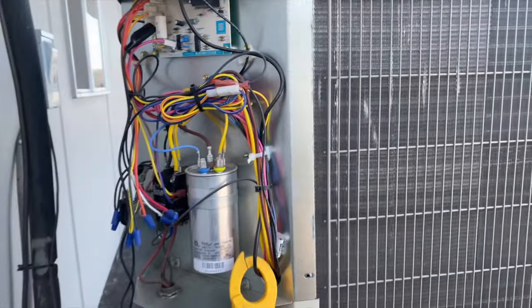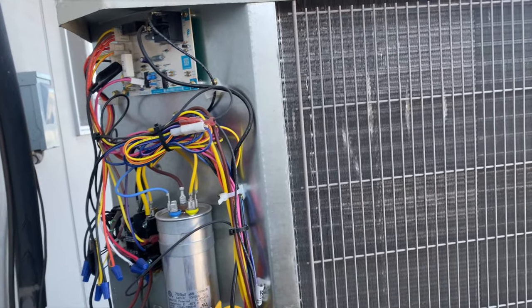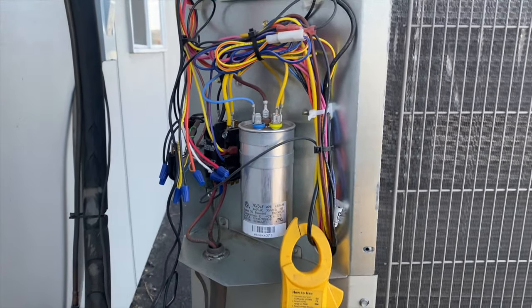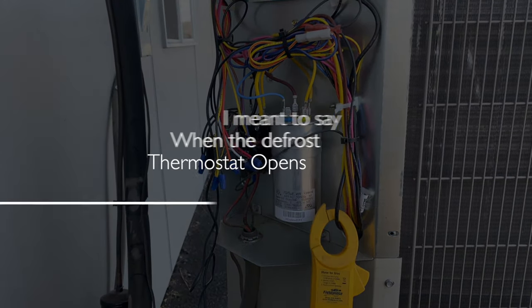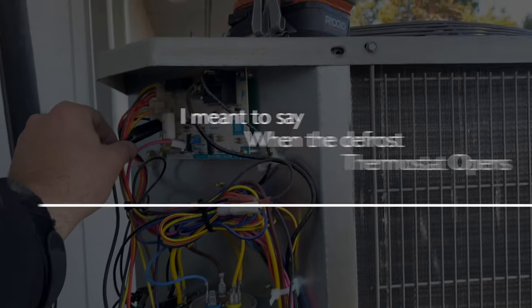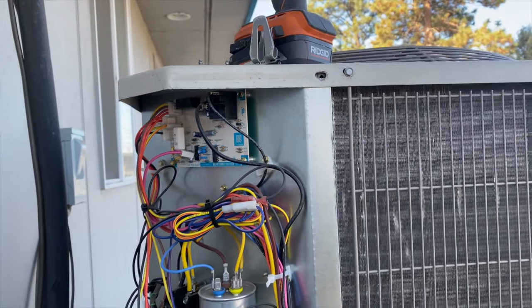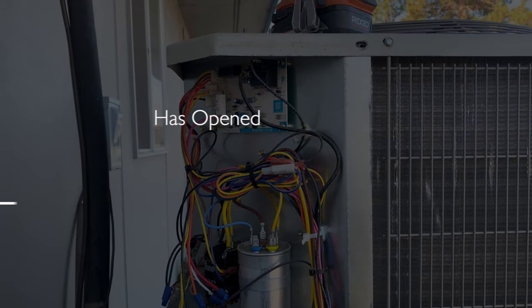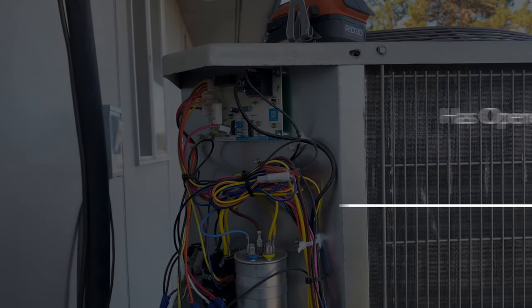I'm not sure exactly for Carrier how long it'll run in defrost, but generally it's going to be 10 minutes or until the defrost thermostat has opened. If we remove this jumper, it'll go back into heat mode because now it thinks the defrost thermostat has opened. That's how you test the defrost mode and make sure your defrost board is working.